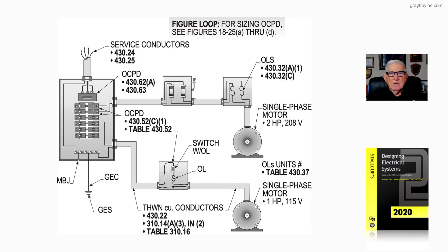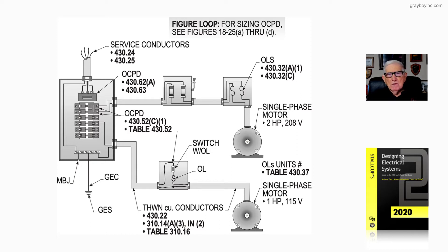We're sizing conductors from Chapter 18 in Stallcup's Designing Electrical Systems, Volume 2. The basic rule is outlined in 430.6A in Appendix I and 430.22 in the NEC. I always suggest users of the code first go to the Table of Contents around page 4 of the NEC. The subject here is motors.